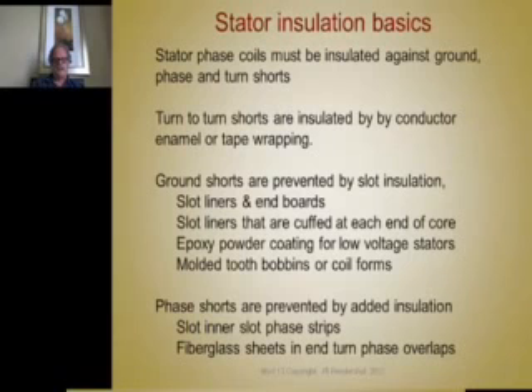Now, phase shorts are prevented by extra, added insulation. You could take the slot liner material and cut it into strips and put it in between the phases in the slot, and in the end turns you use woven fiberglass sheets of insulation material that you put between the phases in the end turns, so that you don't have big potential differences between phases.